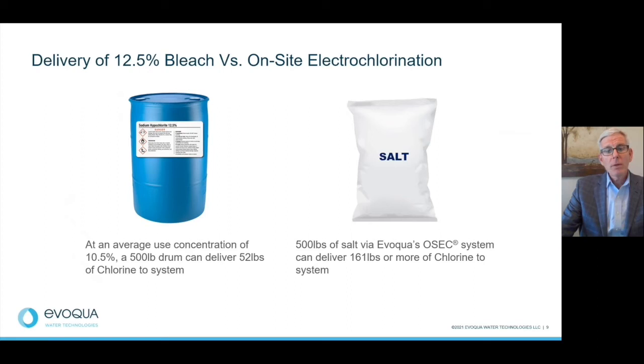Now, 500 pounds of salt via Evoqua's OSEC system has the ability to deliver 161 pounds of chlorine to the system. So for the same carbon creation related to just the transportation of these two supplies, the salt via the OSEC system provides 3 times the disinfection capability. Now, large-scale data centers can use thousands of gallons of bleach in a year. So by choosing to make the disinfection on site, you can make a big impact to reducing your carbon footprint. It will also reduce the risks associated with transportation and handling of a hazardous chemical, as the chlorine manufactured out of the OSEC system is only 0.8% and not considered hazardous.